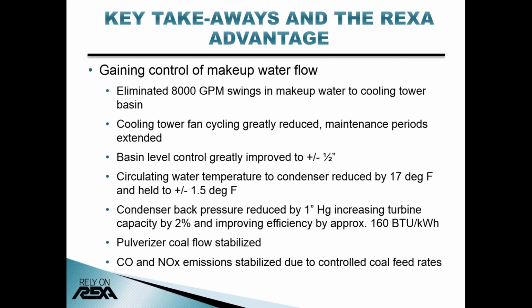Well, that's correct, buddy. And I know you and I talking in the past, you had mentioned a payback time just for buying this one actuator. Yes, sir. Typically, we look long-term in order to justify projects for the facility. And in this instance, going through and stabilizing water flow with the Rexa actuator, the project had less than a 2-month return on investment, which was very good for me, a good feather in my cap, and well received by management. Well, that's terrific. That's a great note to end on here.